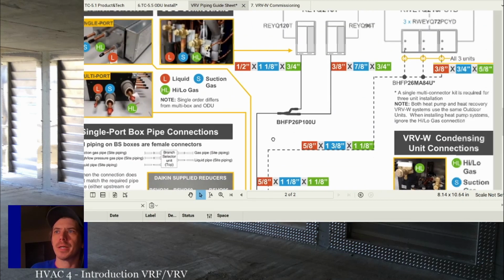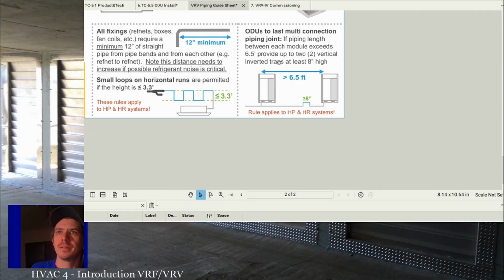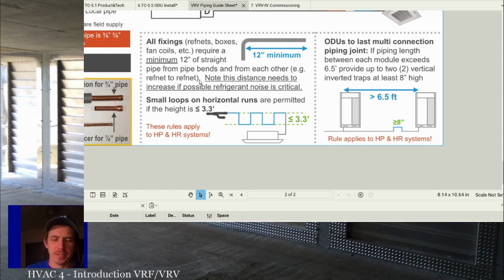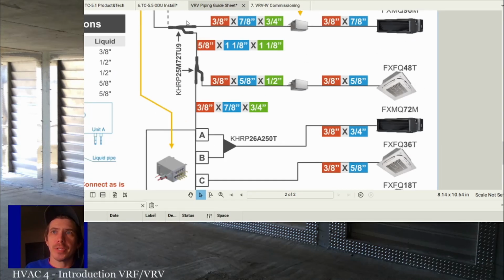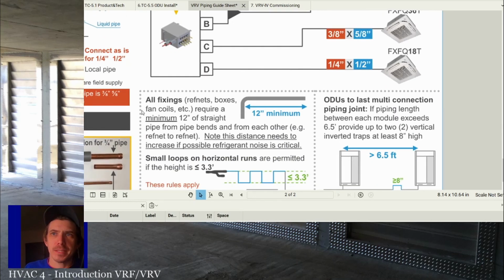The other thing about putting these Y kits in, is it in here? Okay, yeah, here you go. All fittings. And this is very similar between manufacturers. All the manufacturers have the same kind of rigmarole that they're going to tell you about these things. When you're putting in turns of directions or multiple ref nets, so you got this one after this one, and you see how you make a turn and go down? All fittings, ref nets, boxes, fan coils, and 90s for that matter, changes of direction require an absolute minimum of 12 inches of straight pipe from bends and from each other, i.e., from ref net to ref net or Y kit to Y kit, right?